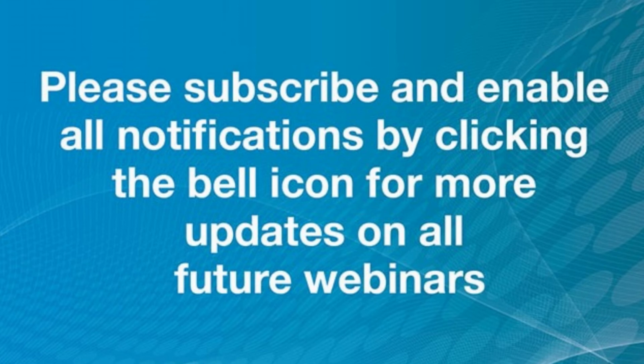Thank you. Our next question, does the MFI have software that is 21 CFR Part 11 compliant? Yes. So our MFI software consists of two parts that work together. Our MFI View System Software is the software that runs the system, and then we have the MFI image analysis software that I mentioned. Both pieces of software are 21 CFR Part 11 compliant. Image analysis maintains that compliance if it's installed on the system computer. So you can export directly from MVSS, which is the View System Software, to image analysis and maintain a compliant workflow.